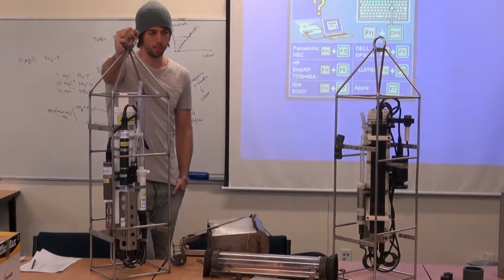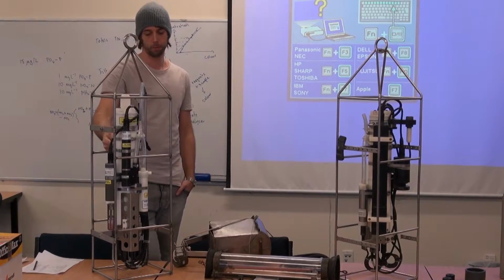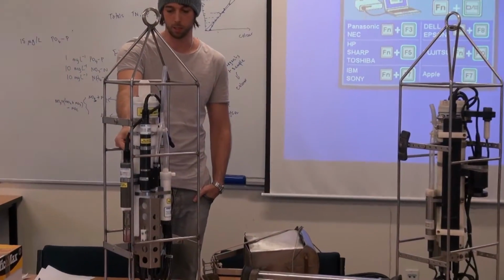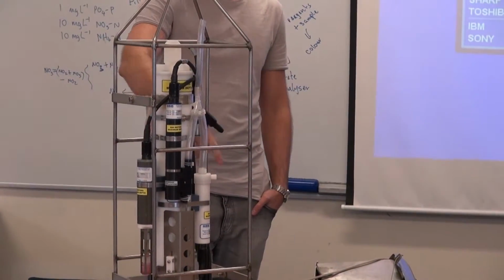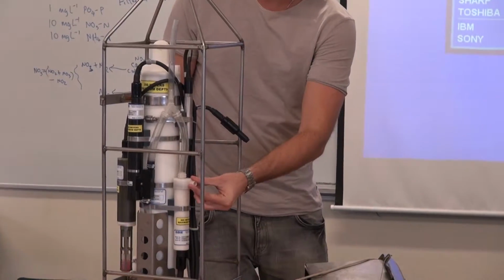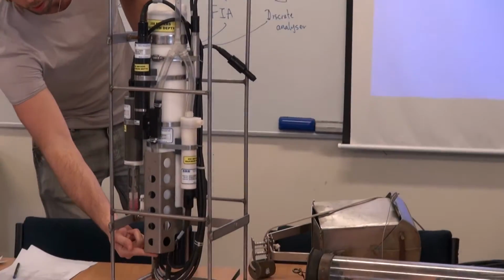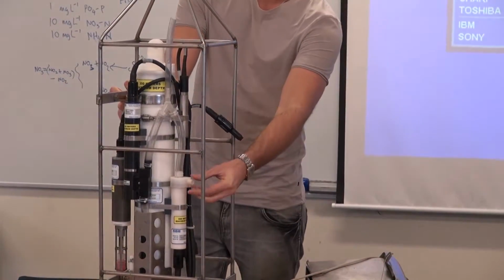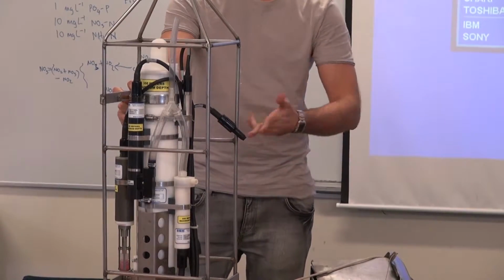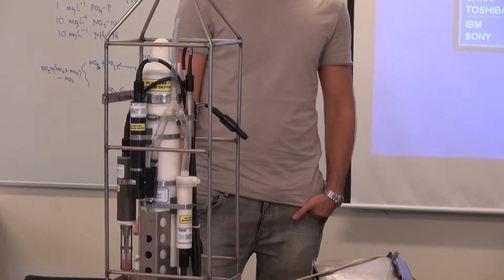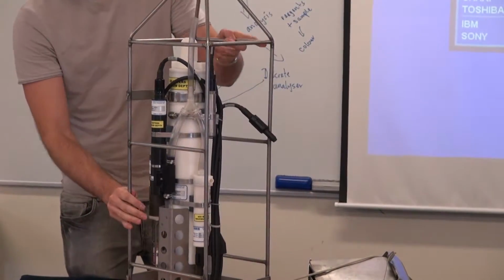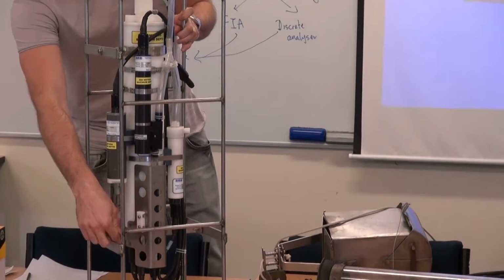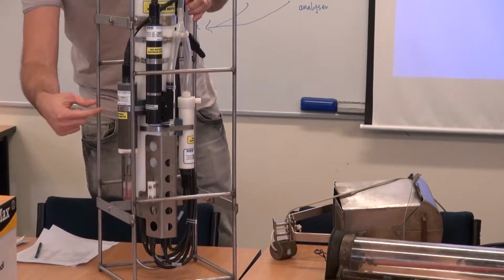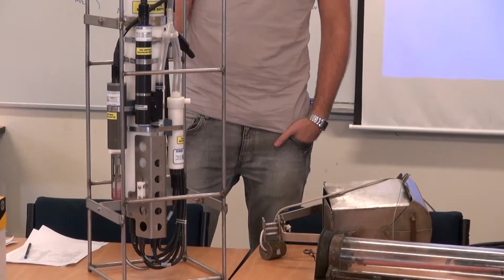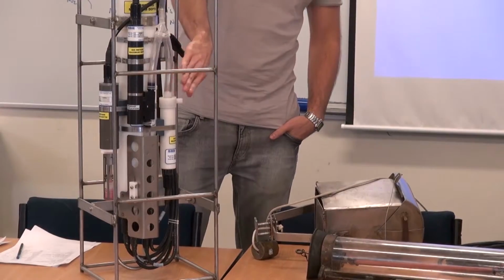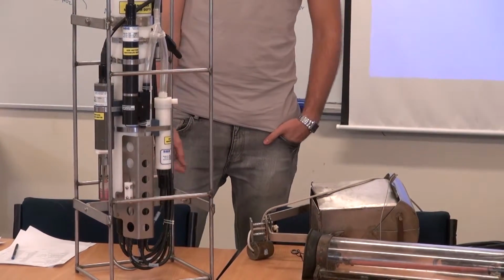The way the instrument works is that it has a pump for the internal sensors, which is the DO and the conductivity and temperature. The pump actually cycles water through the internals here, through these tubes. There's an intake here and an outlet at the bottom of the instrument. So this depth here is where your depth measurements are referenced to. That pump doesn't turn on when you turn the switch on. The switch is here. So down is off, up is on. You turn the instrument on, the instrument will start logging, but the pump won't actually turn on until the water that goes inside these tubes is of a certain conductivity.